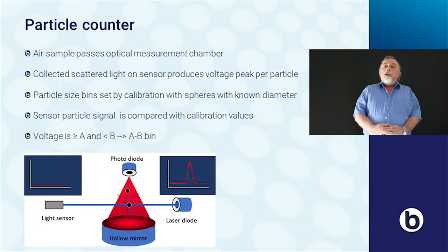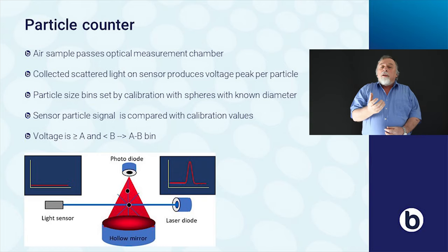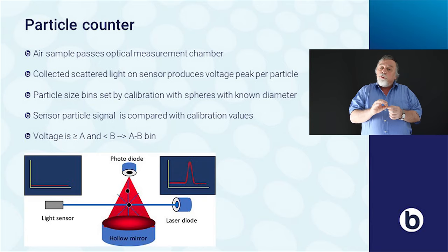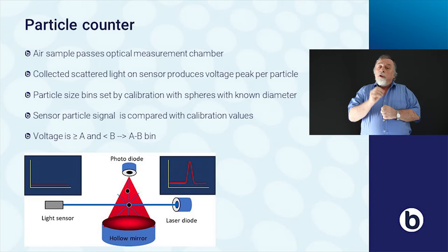A particle counter measures the particles in air. It takes an air sample into the measurement system, and there a particle will pass a laser beam and scatter light. This light will be collected through a hollow mirror onto a sensor, so a particle will produce a voltage peak. This voltage peak can be compared with the voltage peak given by a known particle, a particle which you use to calibrate this instrument.